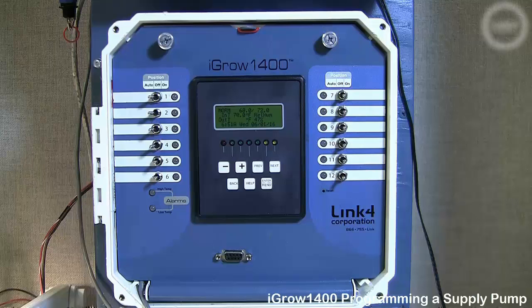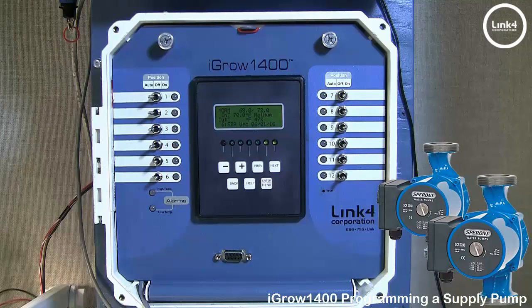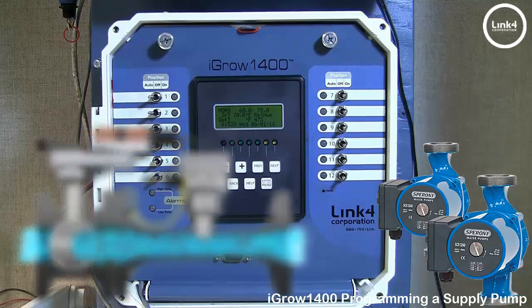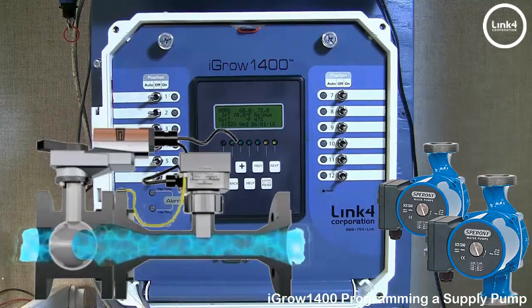In this video, we will discuss programming pumps on the iGrow 1400 controller. You see, when a greenhouse has a mixed valve type heating system, it's often necessary for the controller to manage the system's pumps. Now with the iGrow 1400 controller, you can control up to 5 pumps, each one being activated when the mix valve tied to it opens beyond the minimum threshold of the mix valve.